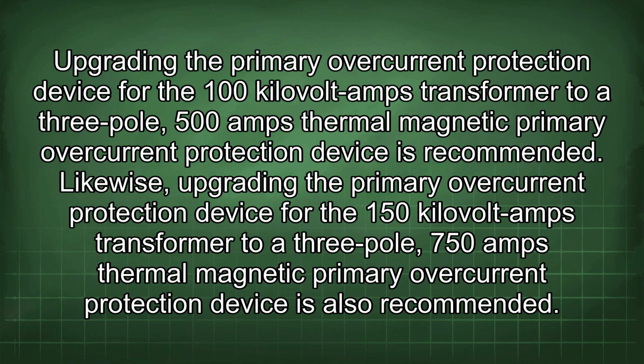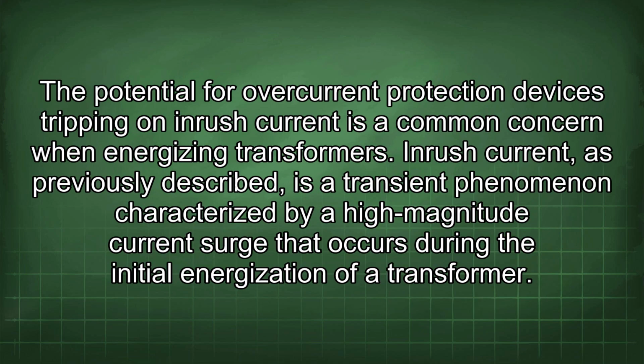Upgrading the primary overcurrent protection device for the 100 kVA transformer to a 3-pole 500 amps thermal magnetic primary overcurrent protection device is recommended. Likewise, upgrading the primary overcurrent protection device for the 150 kVA transformer to a 3-pole 750 amps thermal magnetic primary overcurrent protection device is also recommended. The potential for overcurrent protection devices tripping on inrush current is a common concern when energizing transformers.